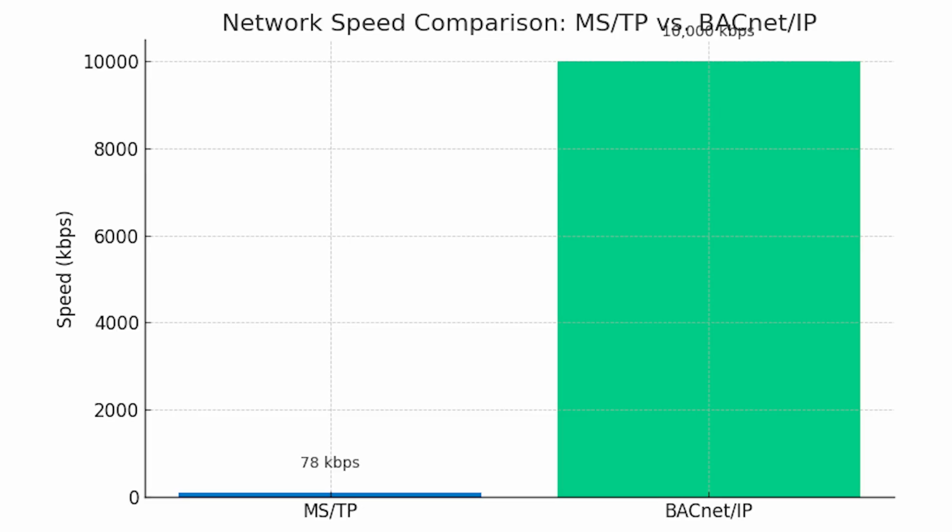Now, difference number three. As you all know, with BACnet IP, we're talking about a minimum of 10 megabits per second, whereas in MSTP, we're talking about 38,000 bauds, 38,000 bits, 78,000 bits. If you do the math, it's not even close. We're talking about orders of magnitude difference.